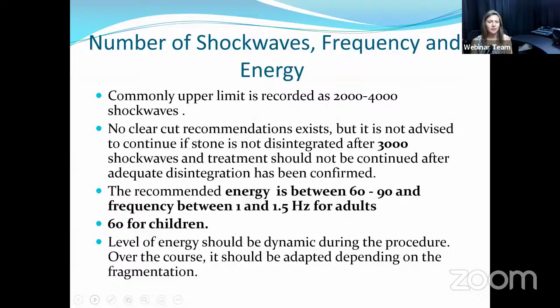Clearly, as we said before, according to the ramping technique, the level of energy should be dynamic and change during the procedure, adapting also to the stone's level of fragmentation. Also, the protocol depends on where the stone is located. So in our experience, we tried different shockwave numbers according to where the stone was. But eventually, we've decided that our guideline is that for a stone located around the kidney or the PUJ area, which is very close to the kidney parenchyma, the patient will not receive more than 3,000 shocks with a maximum frequency of 1.5 Hz and an energy of 60.